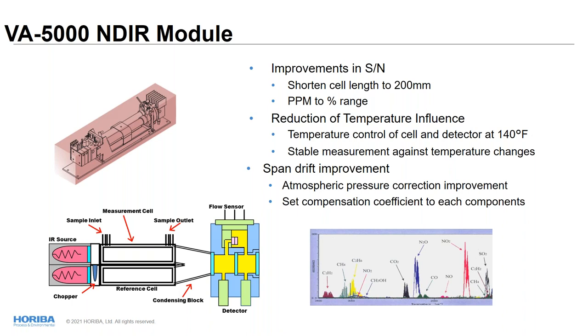So basically, a stable temperature for the cell will give us stability. It also helps keep the sample gas dry and the moisture away. Moisture may capture the sulfur compounds, which damages the cell and causes drift. So we keep the gas dry, chilled to 5 degrees C once and then back to warm conditions, so that we don't have to worry about any moisture and other corrosion. The NDIR cell has atmospheric pressure correction as standard and always works for the compensation of each component.